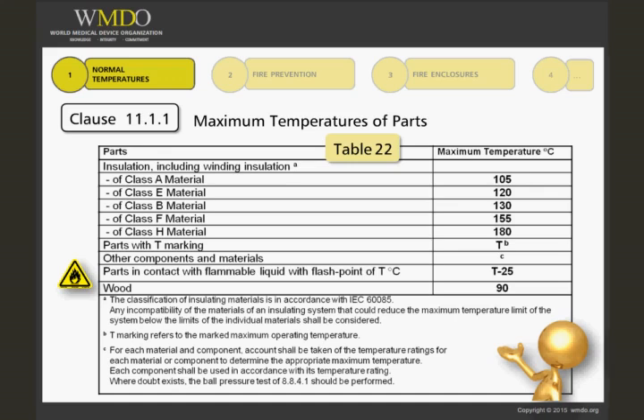We start with reviewing Clause 11.1.1, Table 22, which specifies the maximum temperatures of parts in medical equipment. The first section covers winding insulation. We have Class A through Class H, and these are for equipment with windings such as transformers, motors, inductors, and others.